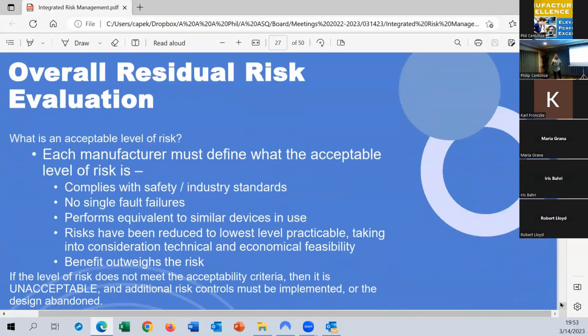So once I've done everything I can to lower the risk, I'm going to determine if I have an acceptable level of risk. And typically, I'm going to say my risk level is acceptable if I've complied with industry safety standards, right? If I have no single fault failures, so if I can detect failures and stop the therapy, or if I have some redundancy, right, so that not one little component failure will make my device not function properly. If it performs equivalent to similar devices, right, this is called state of the art.